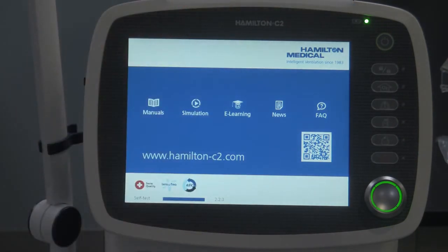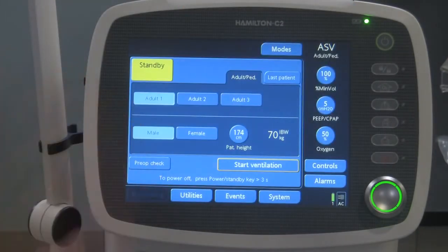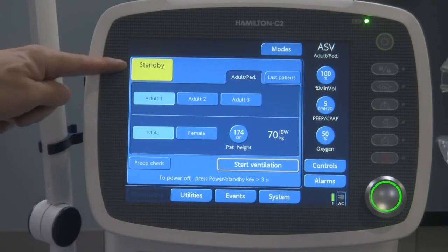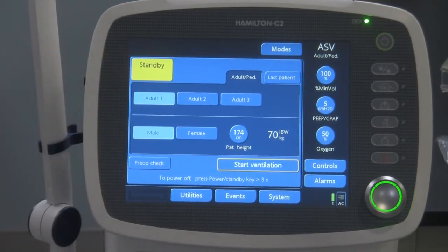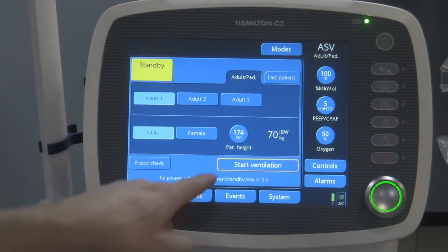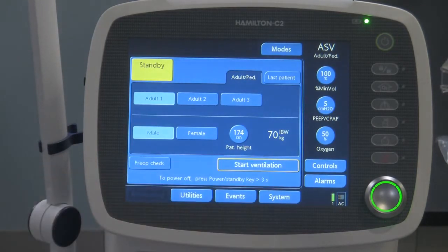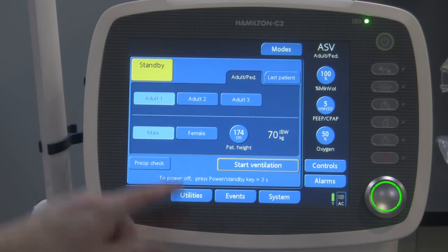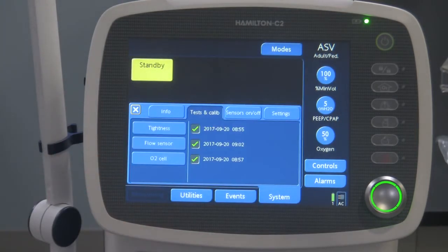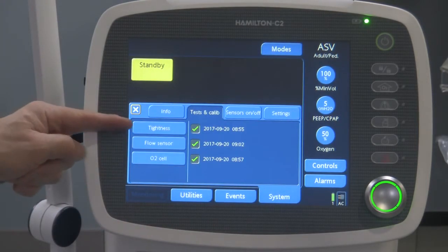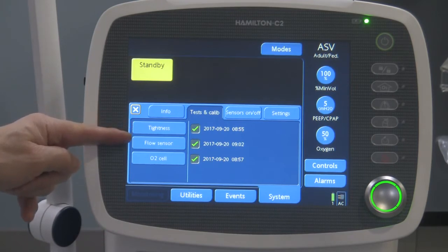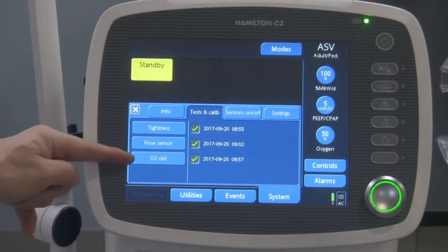It's going to come to a main window here right away. There's the main window right over here. This yellow tab indicates that the ventilator is in standby, and it's going to stay like this until you press that button to start ventilation, once you're happy with the mode of ventilation that you've chosen and you've got those ventilation dynamics programmed or set appropriately. Now to access the pre-use check menu, this is the pre-use check menu right over here, and here are all the pre-use checks. The tightness test, the flow sensor test, and the O2 cell test.